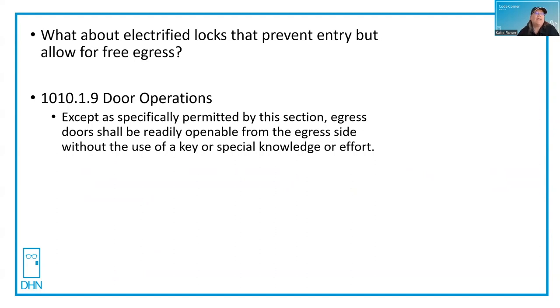For all other doors, section 1010.1.9 for door operations is in effect: except as specifically permitted by this section, egress doors shall be readily openable from the egress side without the use of a key or special knowledge or effort. If it isn't referencing UL 294 here, then you don't need that for standard electrified hardware that allows free egress. You may be able to use this citation to talk to your AHJ and get them to see your side.